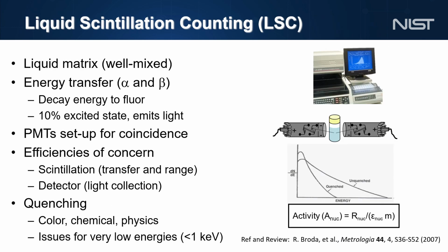In liquid scintillation counting, a radioactive source is measured in a fluor-doped solvent liquid. Decay energy is transferred to the fluor in the cocktail, which then isotropically releases light detectable by 2 or 3 photomultiplier tubes in coincidence. The technique depends heavily on the physical and statistical model of distribution of scintillation photons and their detection probabilities.